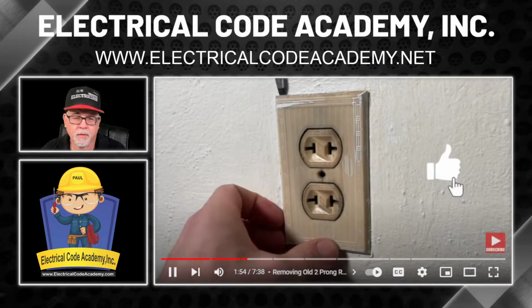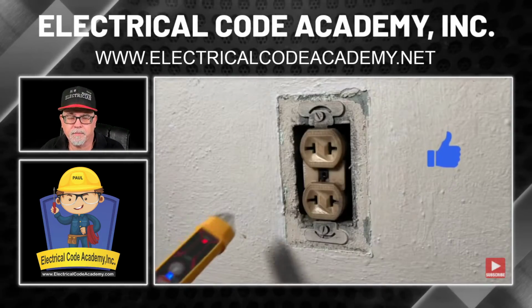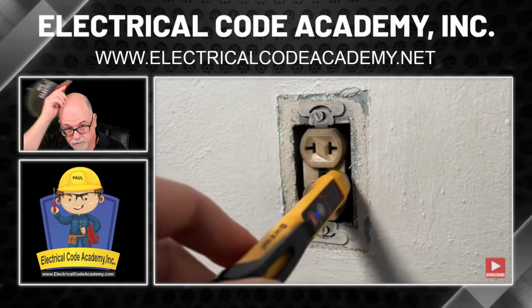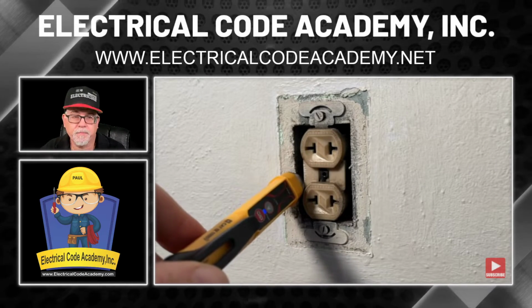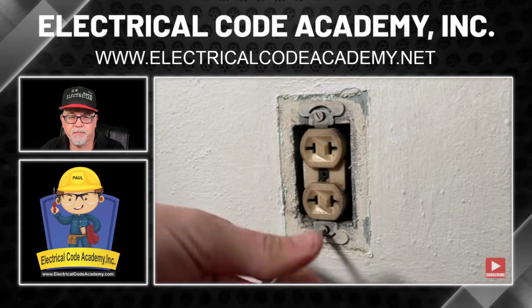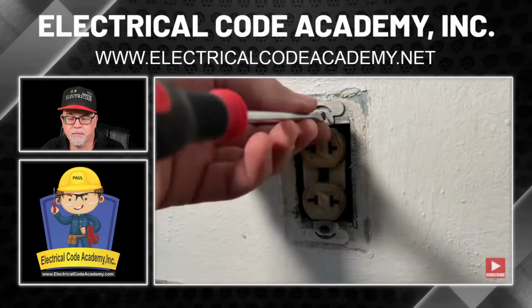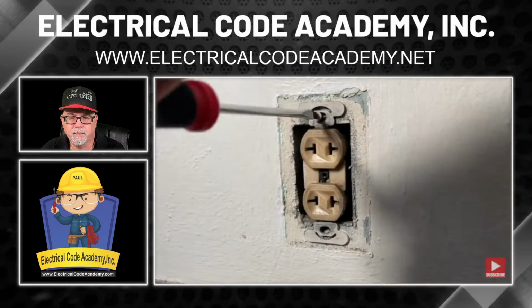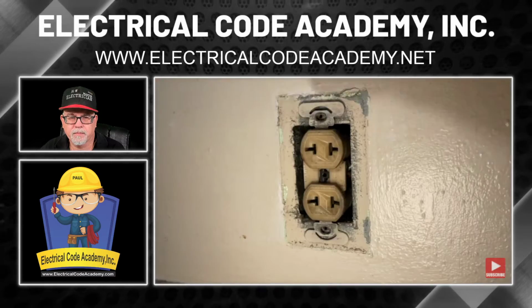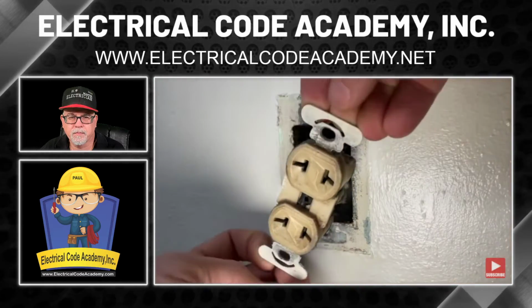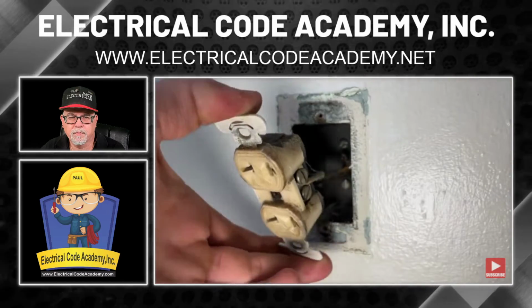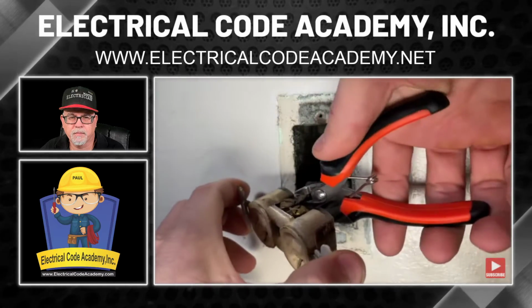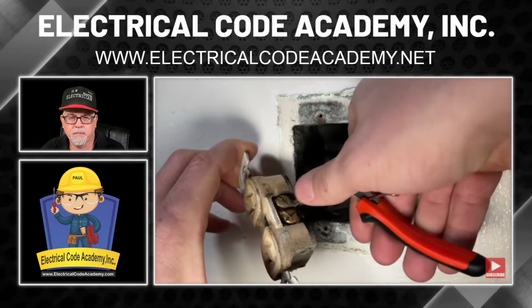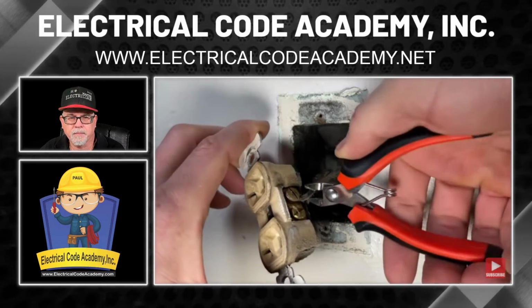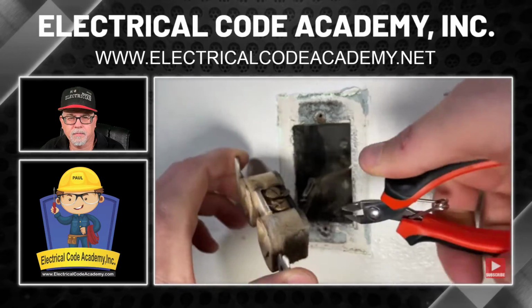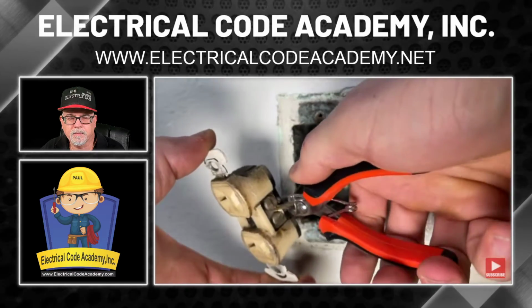Then I undo the screw and carefully remove it to reduce any paint damage. Just double check in here to make sure that no power is going to the box. Then I'm removing the two mounting screws so I can pull the old two-prong receptacle out. I will take a look at what we're dealing with. And here, you really only expect to see a neutral and a hot side. So I am going to take my micro side cutters and just cut that off clean so we can strip new copper for the GFCI.